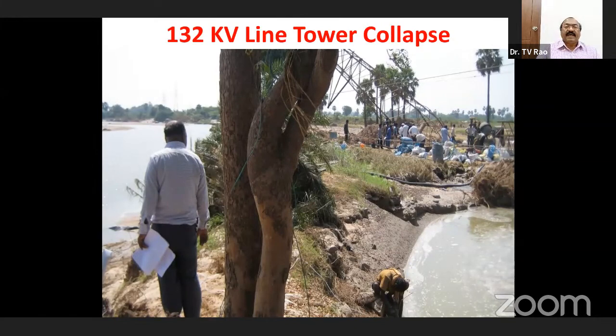The tower is on the bank of the Wagu, but it is not properly elevated. The steel structure should be above the maximum flood level. Because they didn't consider that factor, due to the sudden flash floods, the uprooted palm tree hit the legs of the transmission tower.